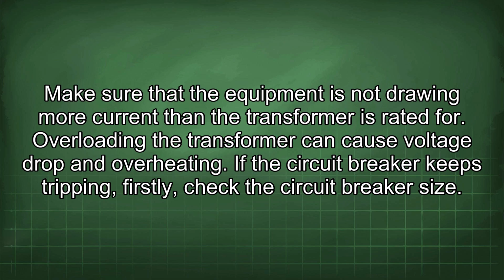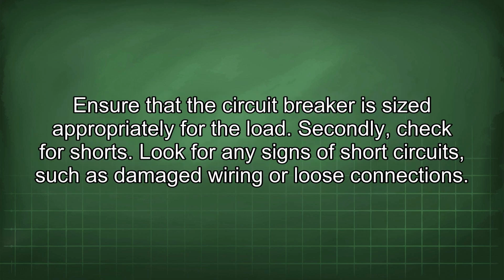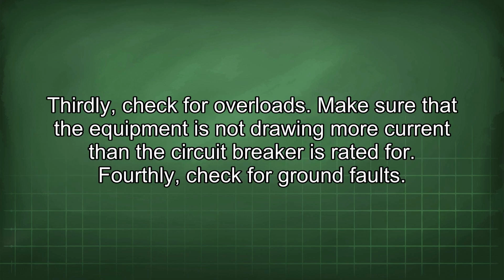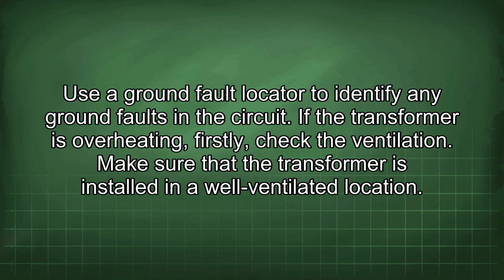If the circuit breaker keeps tripping, firstly, check the circuit breaker size. Ensure that the circuit breaker is sized appropriately for the load. Secondly, check for shorts. Look for any signs of short circuits, such as damaged wiring or loose connections. Thirdly, check for overloads. Make sure that the equipment is not drawing more current than the circuit breaker is rated for. Fourthly, check for ground faults. Use a ground fault locator to identify any ground faults in the circuit.